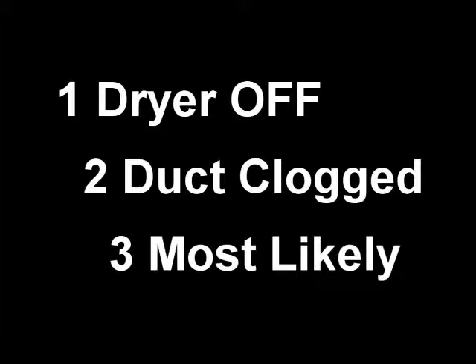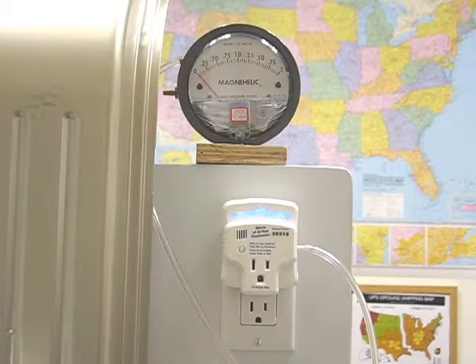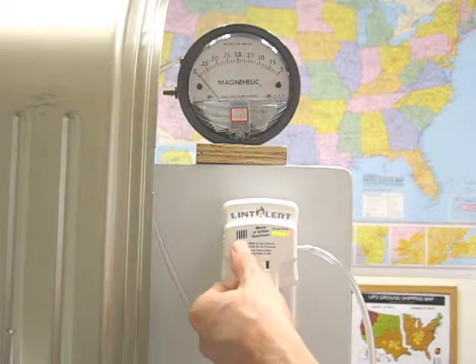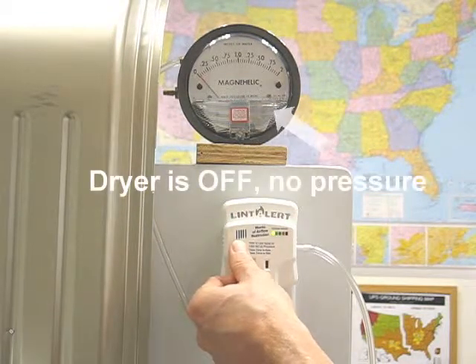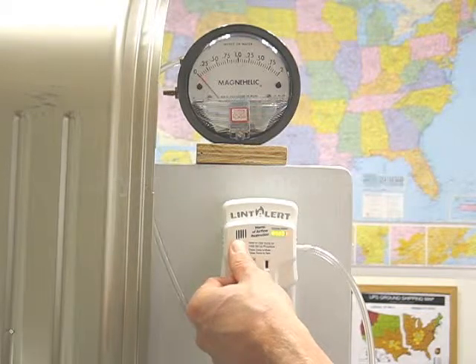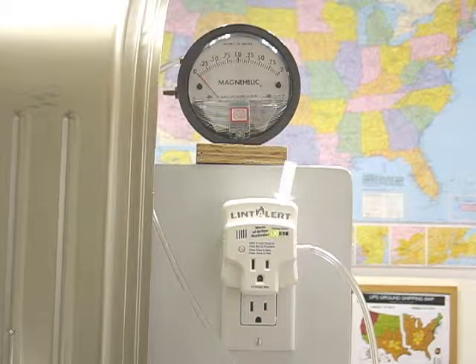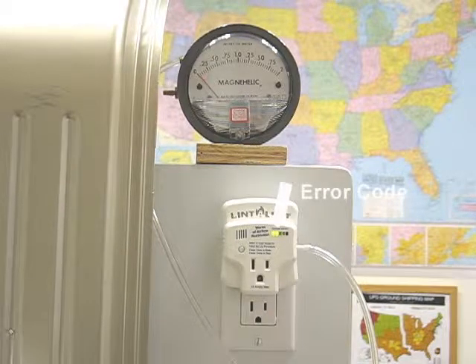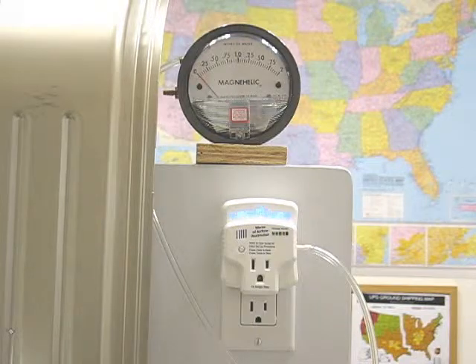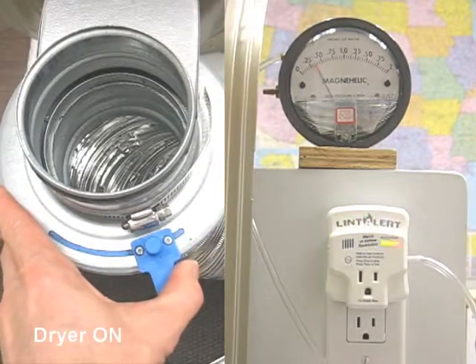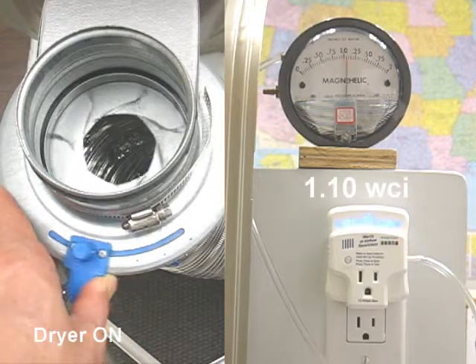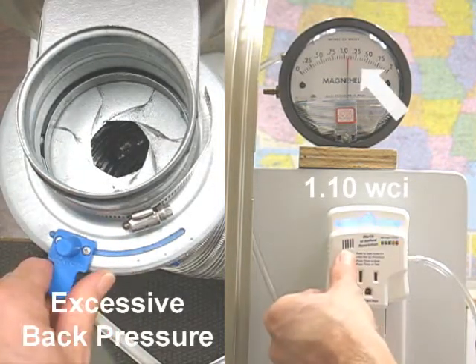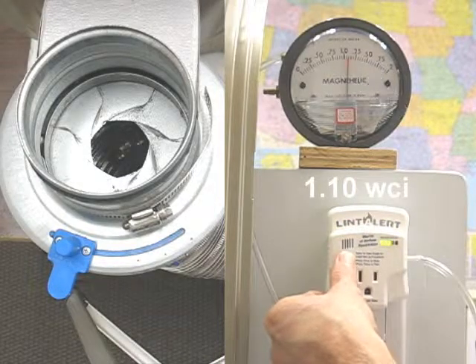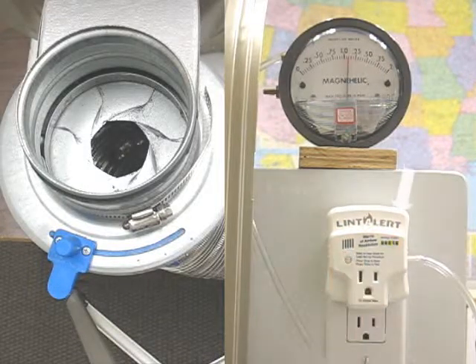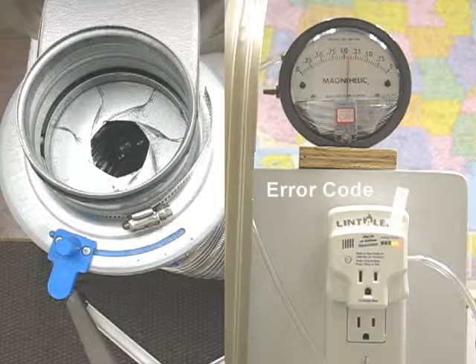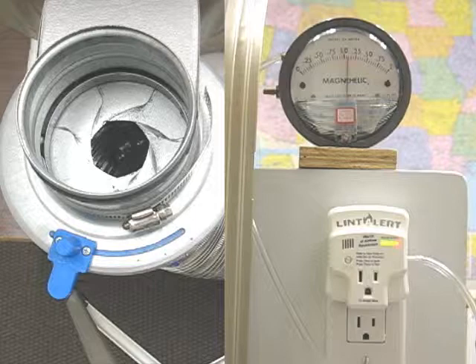First, I'll show that the LintAlert will not allow calibration if the dryer is off. Calibration is achieved by holding the button in for 5 seconds. In this case, since the dryer is not running, the LED light bar displays LEDs 1 and 2, which indicate no pressure found, and will not allow a calibration. Next, I'll attempt a calibration with a simulated clogged duct. In this case, the LED light bar displays LEDs 4 and 5, which indicate excessive back pressure found and will not allow a calibration.